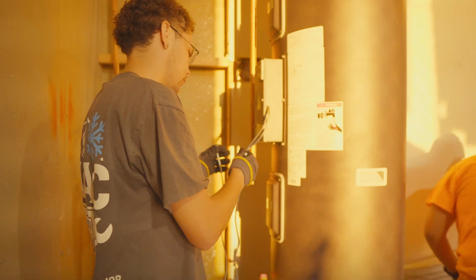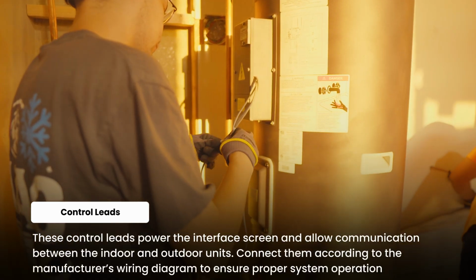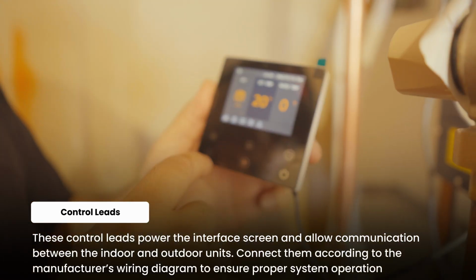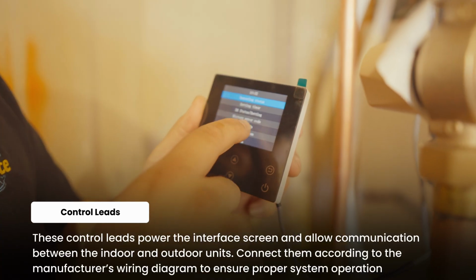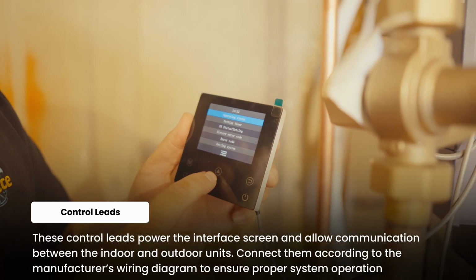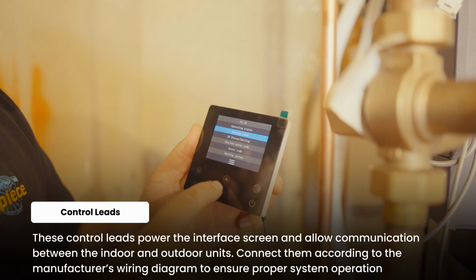After the outdoor unit is wired, run the low voltage control wire to the indoor water heater. These control leads power the interface screen and allow communication between the indoor and outdoor units. Connect them according to the manufacturer's wiring diagram to ensure proper system operation.